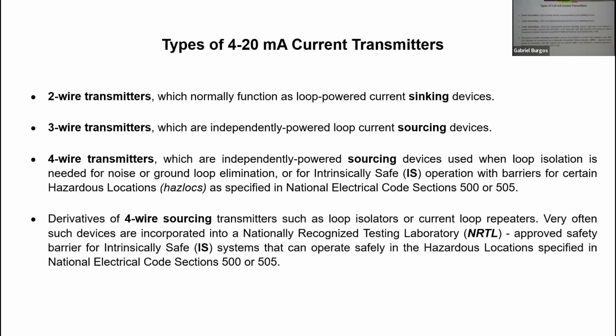But the important thing is it's a sinking device. Everybody understands the difference between sourcing and sinking. Sinking means you're using up energy. Sourcing means you're putting out energy. Simple as that. Now, 3-wire transmitters are independently powered current loop devices, and they're sourcing.